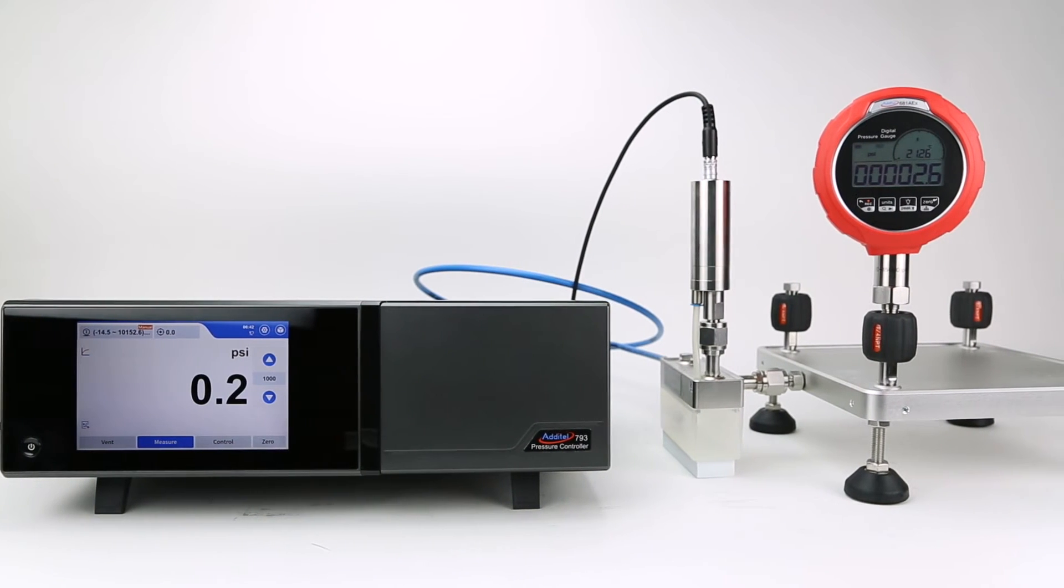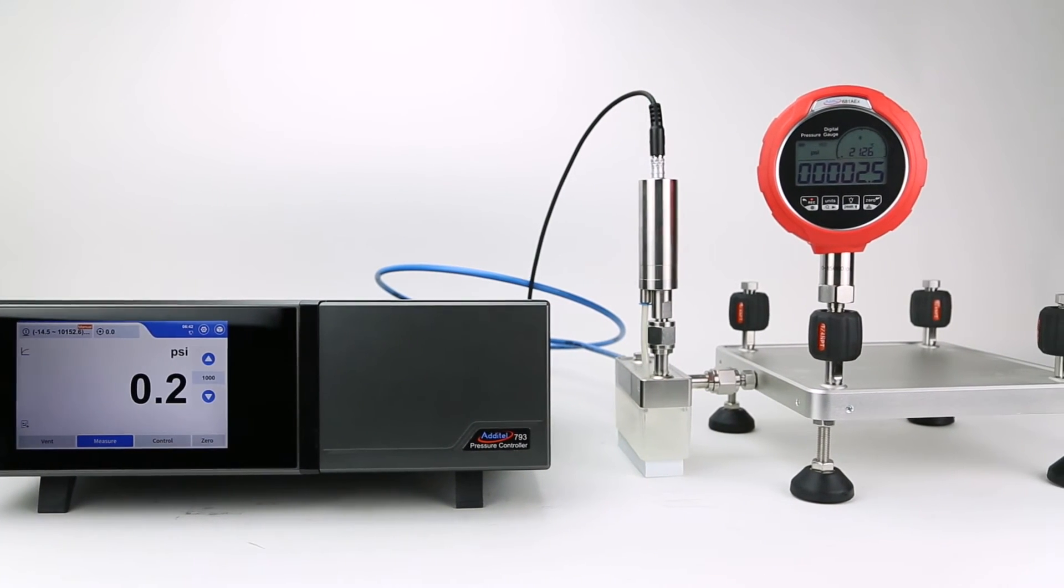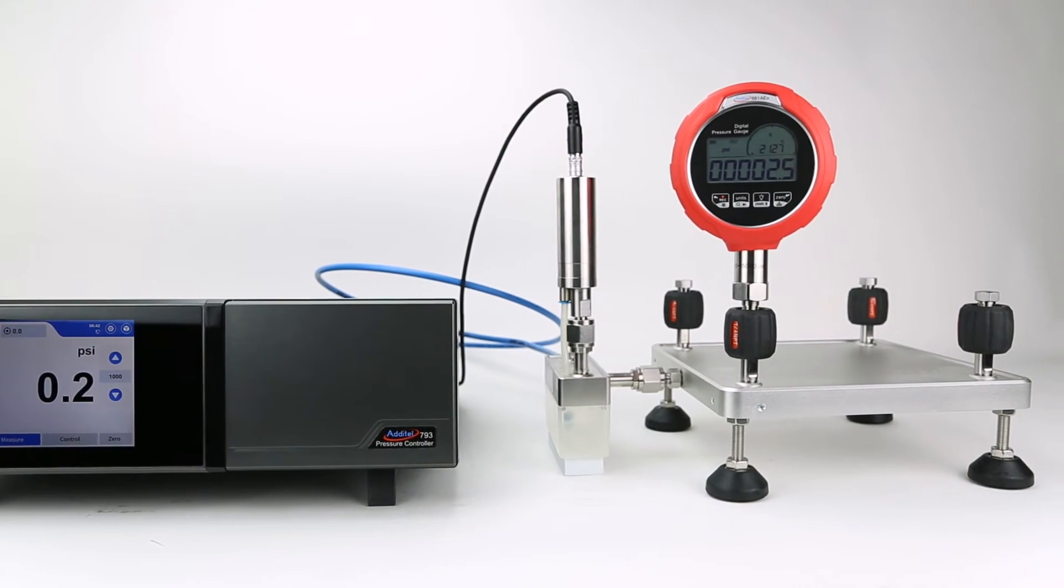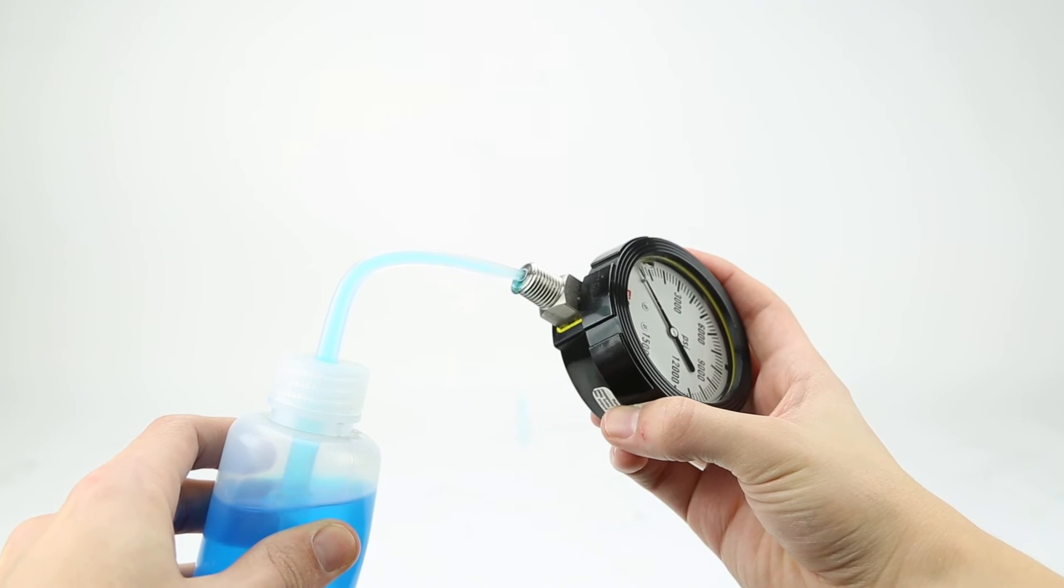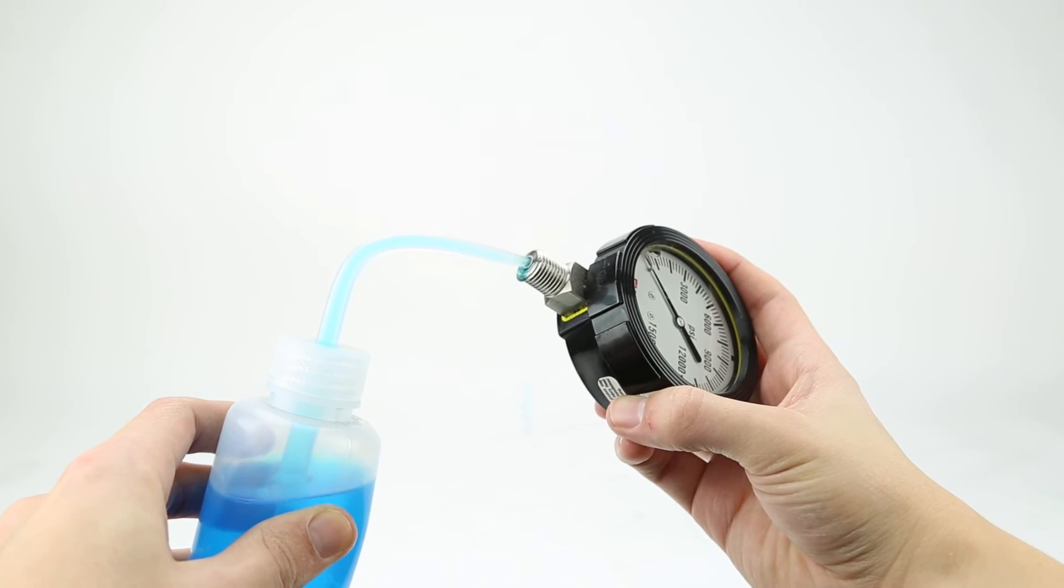The contamination prevention system will now automatically purge any contaminated fluid from your device under test. This can be demonstrated using a pressure gauge that has been injected with a blue color dye to simulate contaminated media.